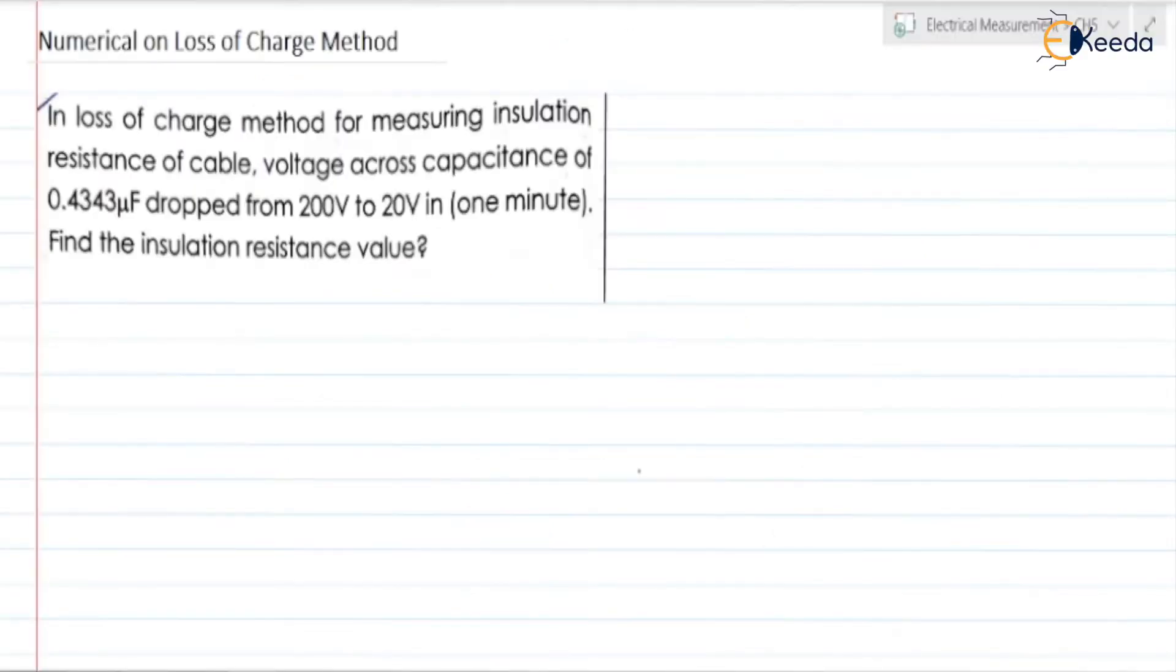Let us read the numerical. In loss of charge method for measuring insulation resistance of cable, voltage across capacitance of 0.4343 microfarad dropped from 200 volt to 20 volt in one minute. Find the insulation resistance value.